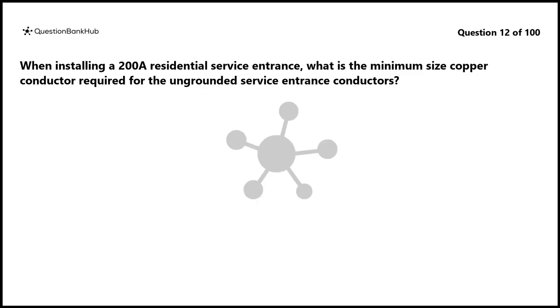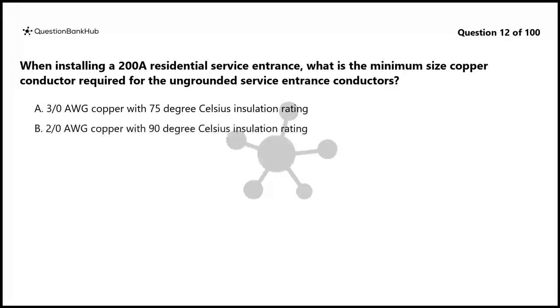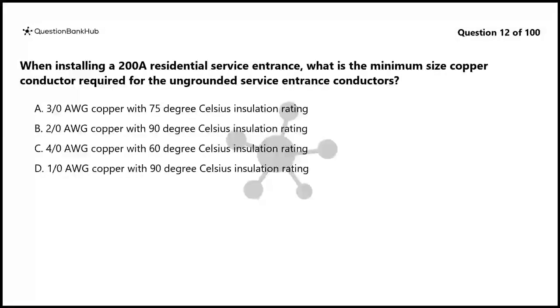Question 12. When installing a 200 amps residential service entrance, what is the minimum size copper conductor required for the ungrounded service entrance conductors? A. 3/0 AWG copper with 75°C insulation rating. B. 2/0 AWG copper with 90°C insulation rating. C. 4/0 AWG copper with 60°C insulation rating. D. 1/0 AWG copper with 90°C insulation rating.